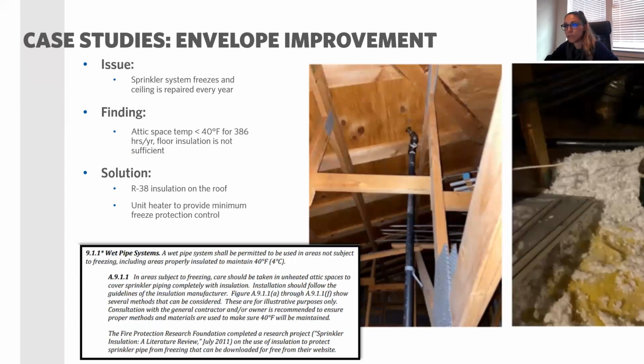And sometimes our findings are not really energy related. So this is a fire station, and they had an attic space which has a wet fire sprinkler system. Even though they are kind of compliant with the code, because they put the insulation between conditioned and unconditioned space, they put it on the ceiling of the first floor, or the floor of the attic space. But because the heads are still close to the roof deck, and there is no insulation on the roof deck, initially the complaint was that the sprinkler system freezes every year, and they changed the ceiling to drywall and paint the ceiling every year.